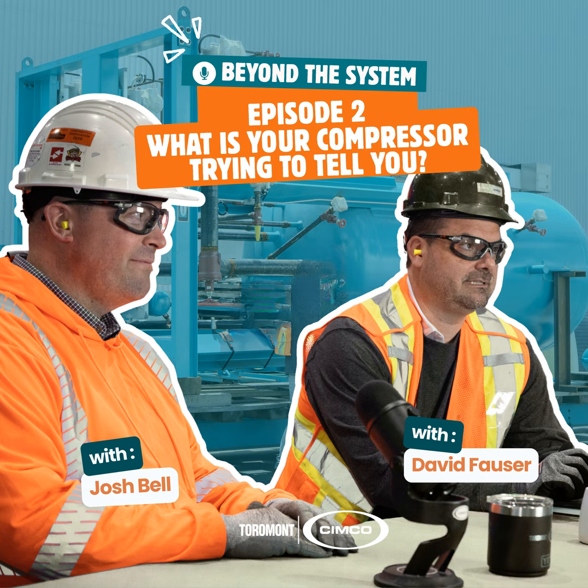near the coupling, it could be one of the discs broke. If you have a direct couple with a bit of a rubber insert, often they're very hard. If you start to see shavings of that around the tunnel or around the compressor, then it could be an issue. And on a belt driven, if you see belts flapping all over the place, maybe they've hit end of life.